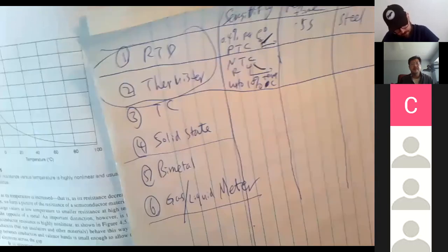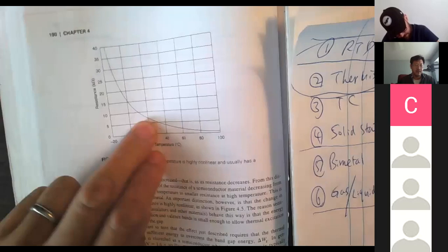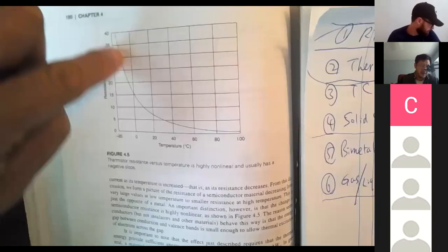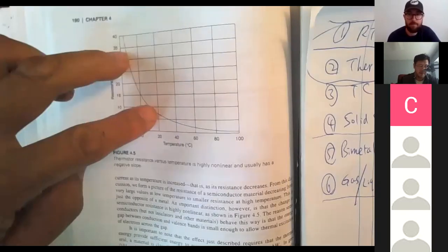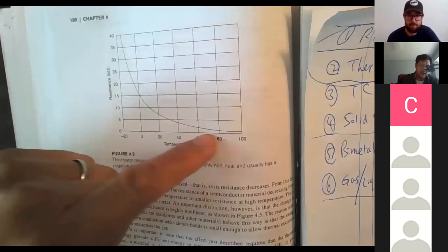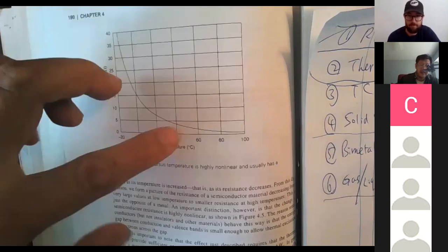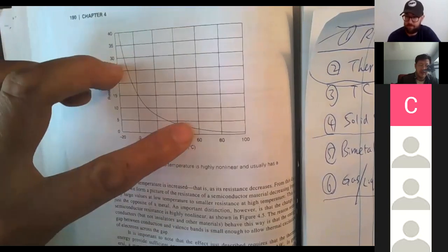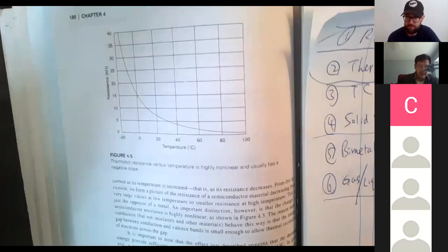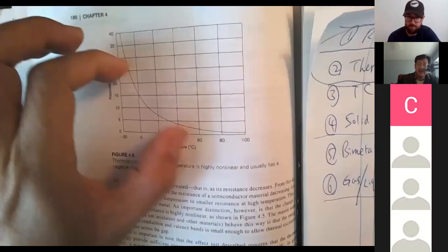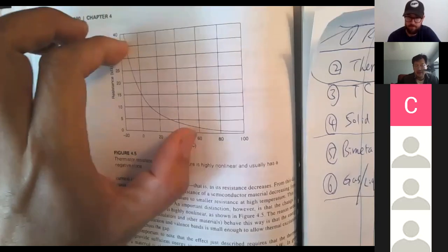So it's extremely sensitive. If you look at here, you'll notice it's very sensitive. The faster it drops, the more sensitive it will be. So it's extremely sensitive right about here. As temperature increases, it's less sensitive. So it's better to measure temperature in this range. This is the perfect range, best range. This will be okay, but not as sensitive. But this is the most sensitive range.